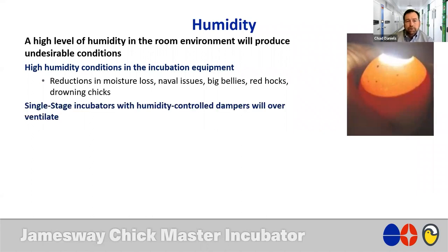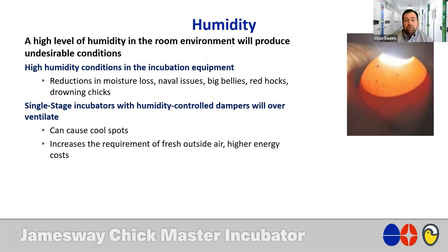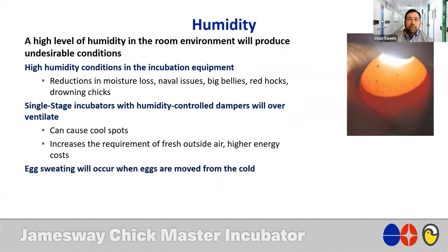In single stage incubators with humidity controlled dampers, they will overventilate if we have high humidity, which, if we overventilate at the wrong time of incubation, can cause cool spots in the incubator. It also increases the requirement of fresh outside air, so you'll have higher energy costs. And then if we have a high humidity environment, it makes it easier for egg sweating to occur, not only when we move eggs from an egg room, say, to an incubator room, but also at the time of unloading eggs on the egg dock.